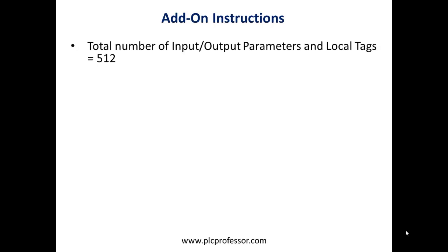The total number of input and output parameters and local tags for an add-on instruction is 512. That may not sound like a lot, but when you think about how to use and create add-on instructions, if you're approaching 512, you've really gone beyond what an add-on instruction was meant for. Add-on instructions should be kept very simple. If you're going to have that many input/output parameters and local tags, you probably should be nesting your add-on instructions.